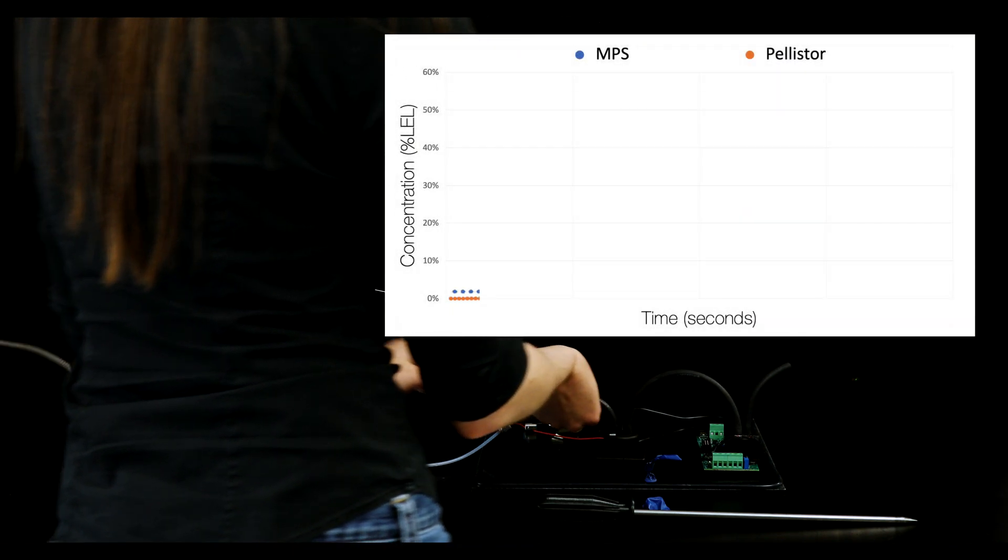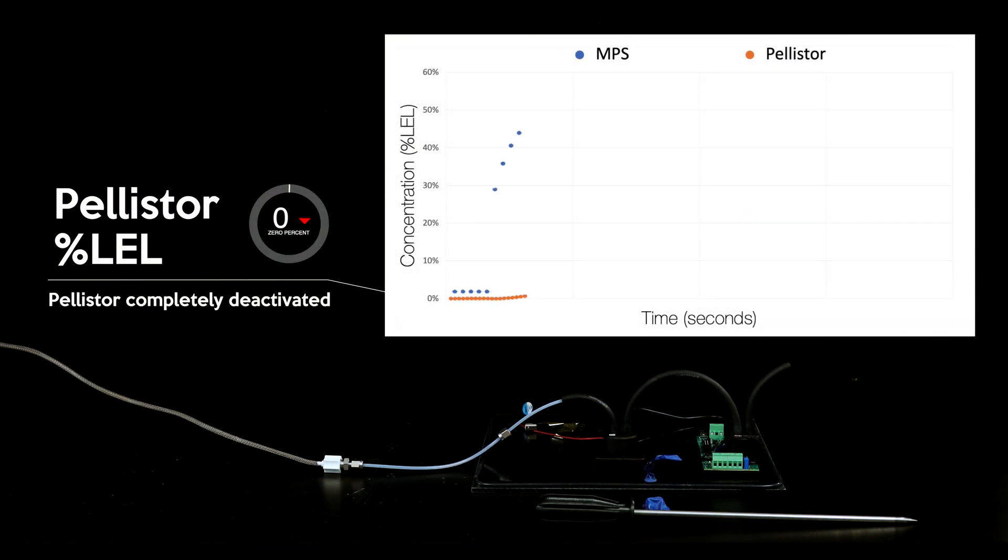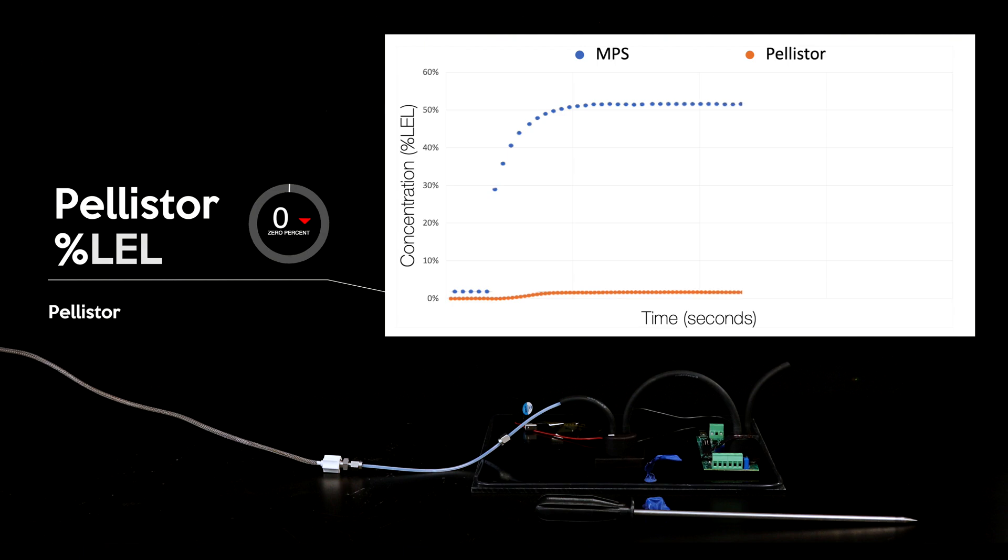A quick bump test with 50% LEL methane shows that the pellistor has been completely deactivated and doesn't respond to methane. This is due to a permanent reaction between the hot catalyst and the silicones, which has ruined the sensor.